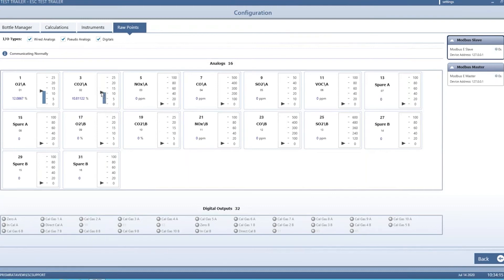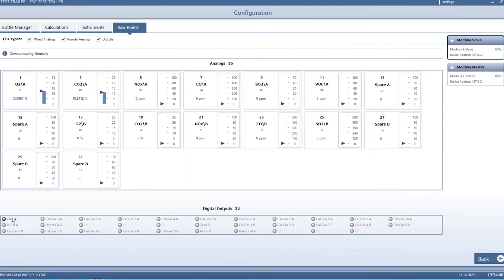At the bottom you can see your digital outputs, which are typically going to your gas solenoids to turn your cal gases on and off. The gray color means they're essentially all off right now. If you want to troubleshoot, you can manually toggle them from here to turn them on and off. You can see what they look like when actually turned on — the color fills in to indicate that digital is energized.